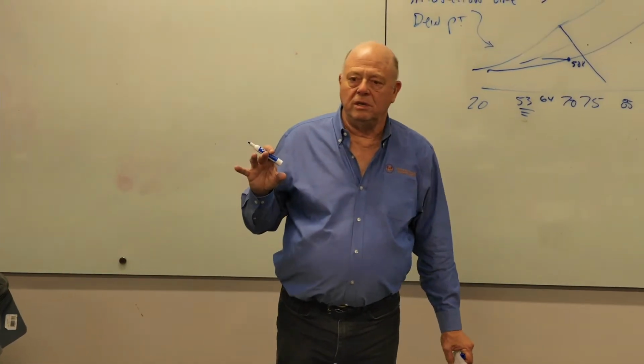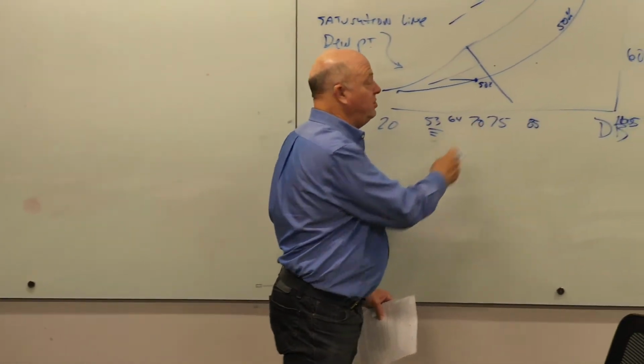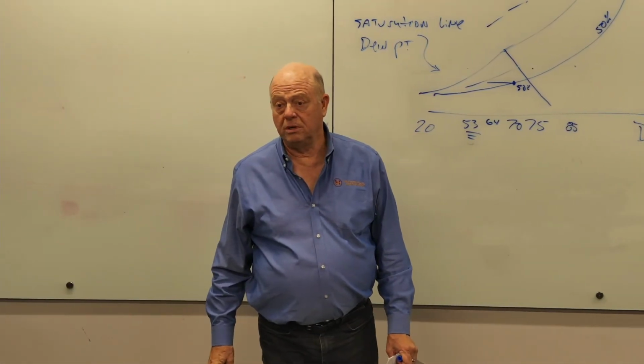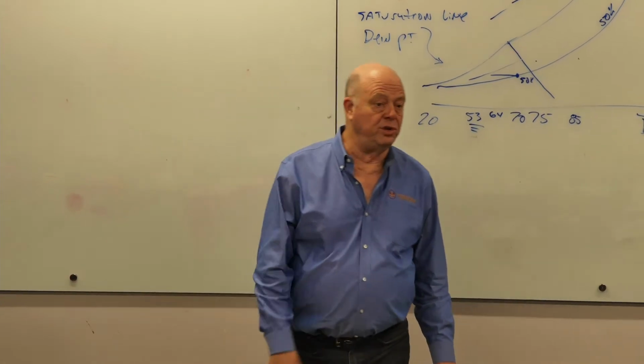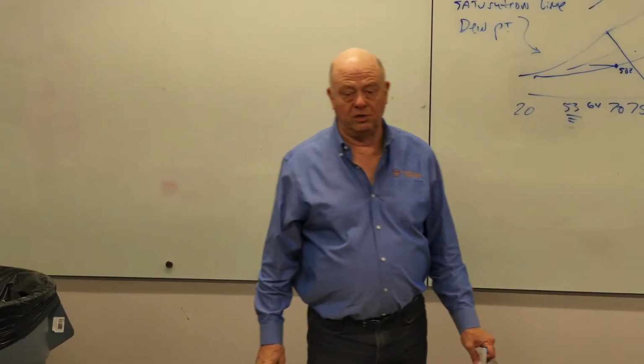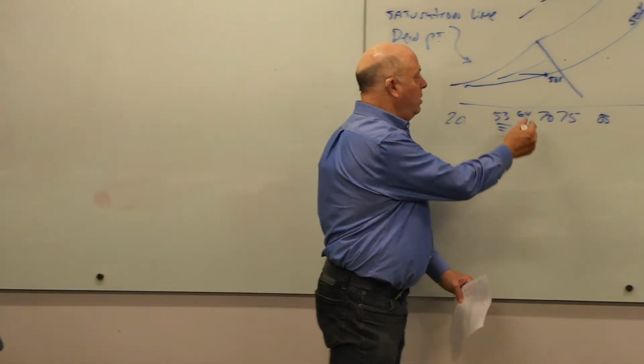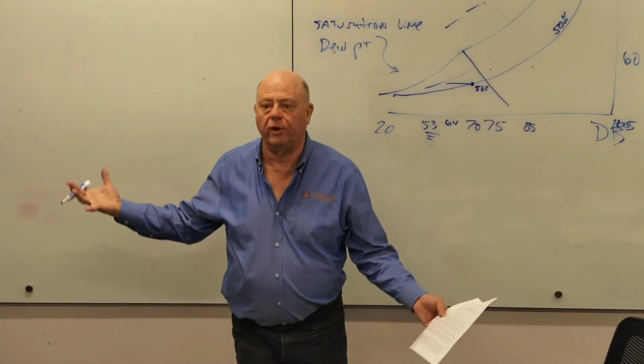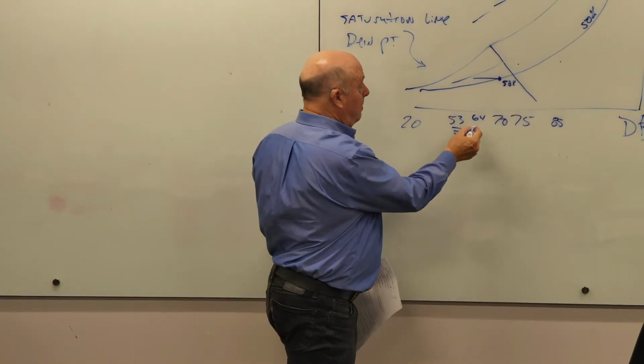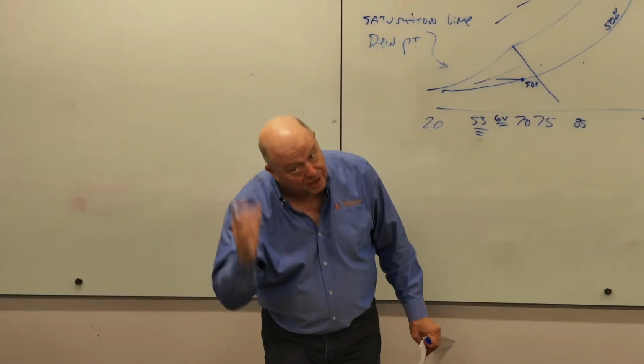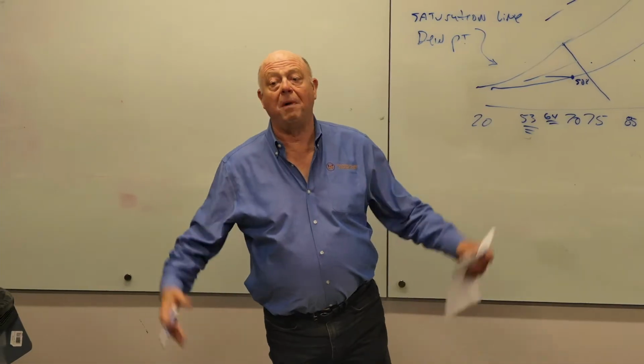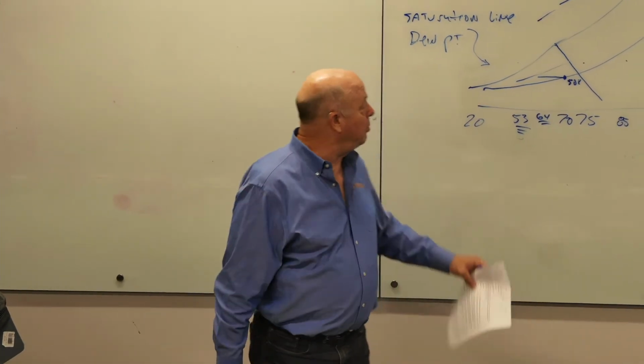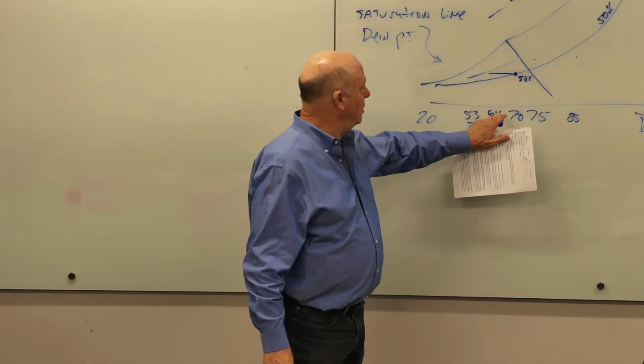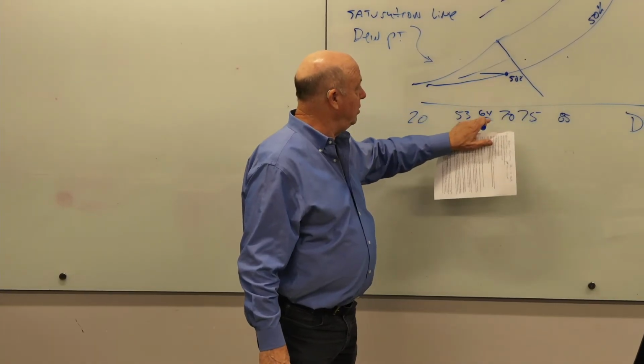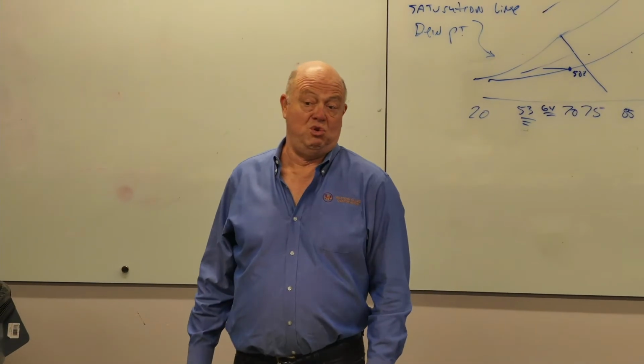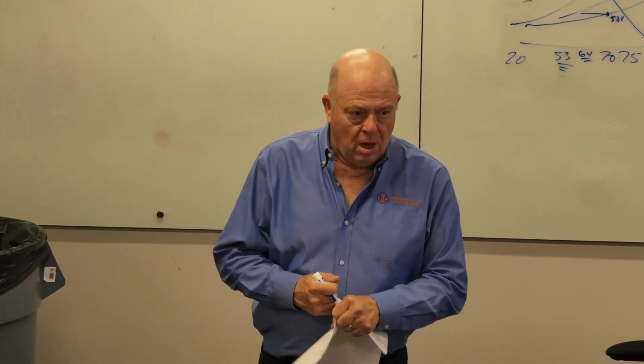The solution is you have to basically change your design parameters. And we reverse engineered that many times in many ORs over the last 15 years to where, okay, since 70 and 50% isn't where they're going to run it, and I've got to end up probably around 64, and I got to be under 60%, what's my new design criteria? And then you end up probably saying that it's now going to be about maybe 67 and 50, or maybe you even shoot for 64 if you can do it.